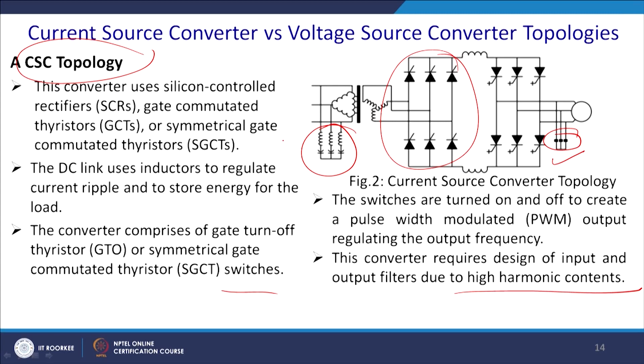This inversion operation is done through GTO or SGCT. The switches are turned on and turned off to create PWM, pulse width modulation, output regulating the output frequency. The converter requires input and output filters to be designed due to high harmonic content. So, these are the filters you have to place, and ultimately this will reflect back, and you have to suppress the filter also at the input of the supply, otherwise the utility's power quality will degrade.